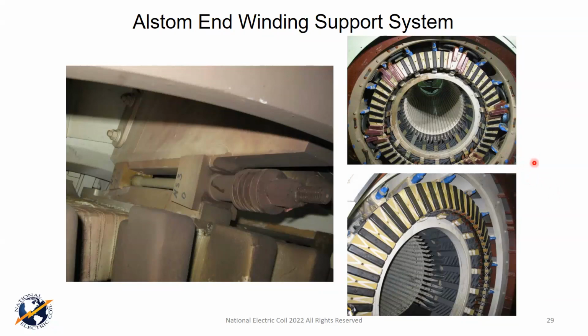18 months. That's what you call design obsolescence, okay? And I don't think it was designed that way, honestly. That's not true. But the fact that it was out of warranty and the fact that you don't get stress corrosion propagating that way, let alone I was there for 3 days and I told them I haven't smelled ammonia at all. And I said, there's a way we can find out. We can bump test, and at worst, we're going to waste a day. But I want to know, and there's good reason.